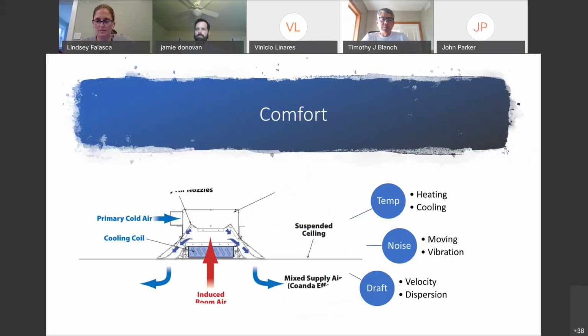So we said, well, what should we pick if we really care about our occupants' comfort? We picked chilled beams, 4-pipe active chilled beams, so we could heat and cool with them. That's a little diagram I stole off the internet, and you can see parts of it are missing. If you don't know what a chilled beam is, it's a very simple device. It has a coil that the room air gets induced up through, and gets cooled or heated. In this case, this is in cooling mode. So you're running medium temperature chilled water through it, which means 57 degrees, which means it doesn't condensate.